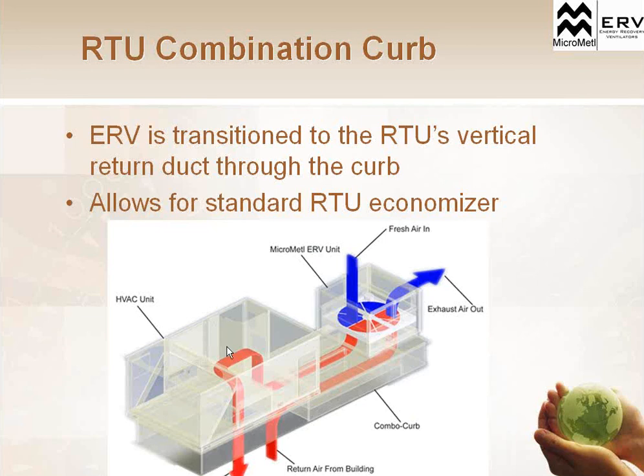Or we can do it in a roof curb. We commonly use with MicroMetl a combination roof curb, or for short, a combo curb. It would be one single roof curb that we lay on the roof, and we drop the energy recovery unit onto that curb, as well as the rooftop unit. And that horizontal duct transition is built into the roof curb. It's built in to reduce the static hit that we would take in the system.